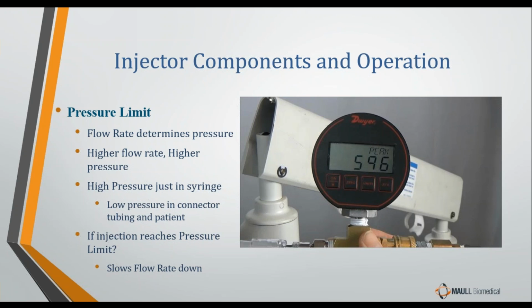Now, if something were to occur, and for some reason we did actually hit that pressure limit in the syringe, let's say we did hit 600 psi during the injection, the injector does not shut off. This is an important point that is also a cause of confusion sometimes with the operators. If we hit the pressure limit, the injector doesn't shut off. We don't want to stop the injection. What the system does, to prevent the pressure from rising higher and higher, is slow the flow rate down.